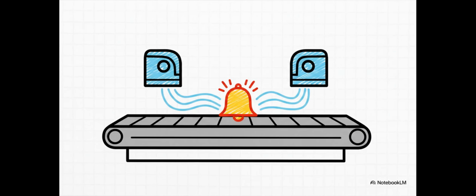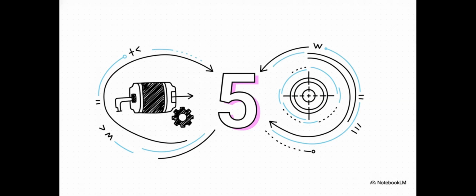So how's this actually used? First up, building signal difference alarms for redundant temperature or pressure sensors. If one sensor drifts, ABS guarantees a positive offset. This lets you trigger a single, super clean, high-limit alarm. It's also absolutely perfect for PID loops. Say a motor's target must stay within plus or minus 5 units. Calculating absolute error instantly defines rock-solid in position or at set point windows, entirely without writing any messy, complex logic.